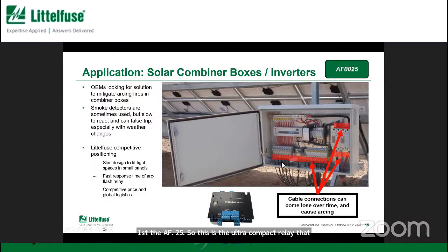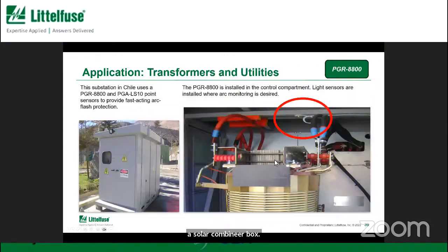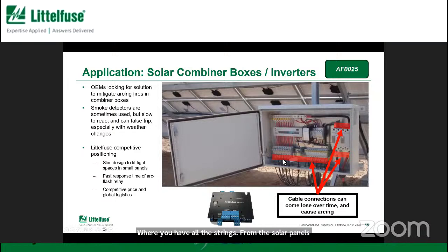First, the AF25. This is the ultra compact relay that I talked about. There may be small panels like this where any loose wiring is a concern, and this particular one is a solar combiner box where you have all the strings from the solar panels coming in. There's a lot of wiring connections, and if you have loose wires, over time they can come loose and create an arc across the terminals. With a tight space, you may only need one sensor and have a relay that you want to fit in a tight spot. So that is a good place where the AF25 could fit.